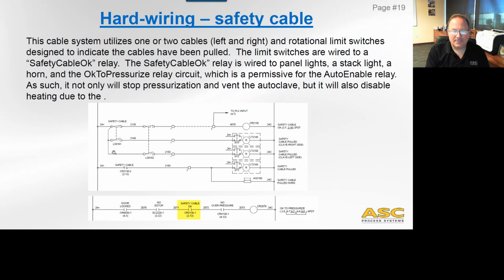So, and we have the safety cable. That's the hard wiring for the safety cable. This cable system utilizes one or two cables on the side of an autoclave, and rotational switches on the outside of the clave tied to a rod, and those are used to basically tie to a full-length safety cable down the length of the autoclave, and that is then tied to lights, but also a relay called safety cable OK.